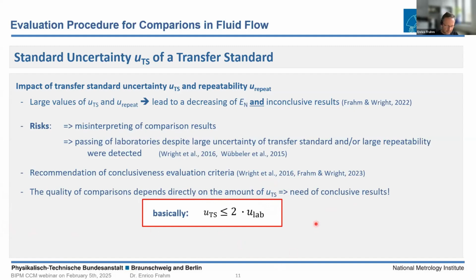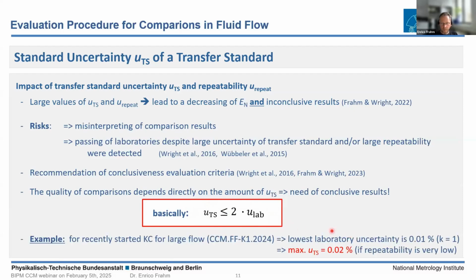So this leads to one of the simple evaluation criteria behind this discussion: the maximum uncertainty of the transfer standard should not exceed twice the lab uncertainty. This is a very simple formula and really important, and the simple background of the discussion. Let me give you an example. For the recently started key comparison for large flow, the lowest lab uncertainty is 0.01% standard uncertainty. So the maximum allowed uncertainty of the transfer standard, to get proper results for this comparison, is only 0.02%. And it's really hard to get such a very sophisticated meter under test as a transfer standard in the field of fluid flow.